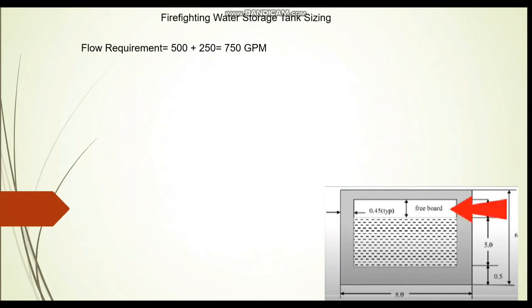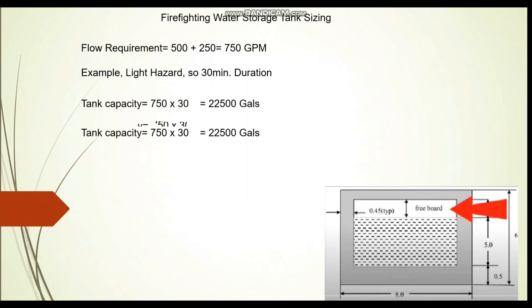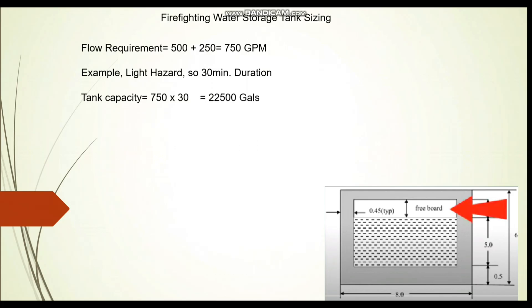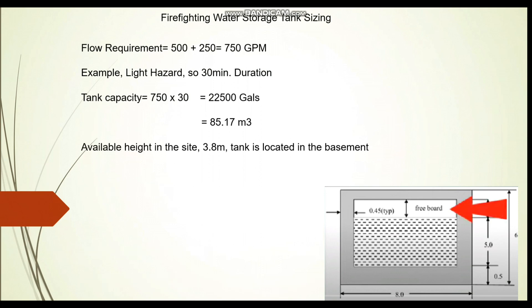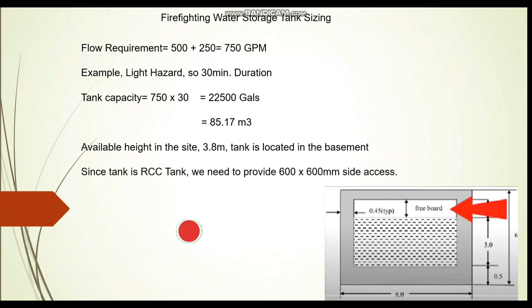For our project with a standpipe system classified as light hazard, the fire pump flow is 750 GPM. Using the 30-minute duration from the NFPA 13 table, the tank capacity equals 750 GPM multiplied by 30 minutes, giving 22,500 gallons. Converting to cubic meters, we get 85.17 m³. The tank is located in the basement with an available height of 3.8 meters.